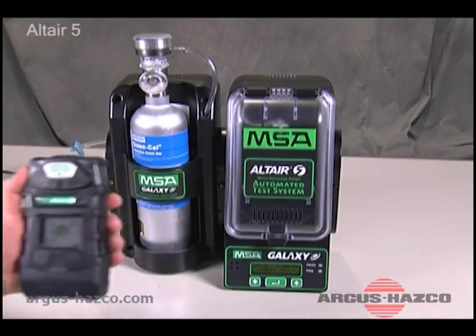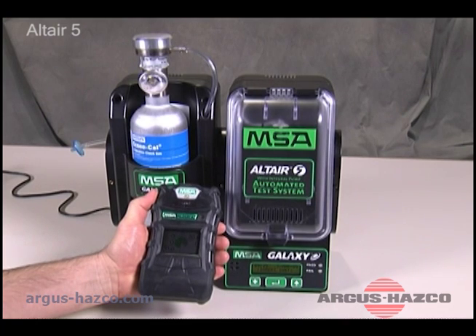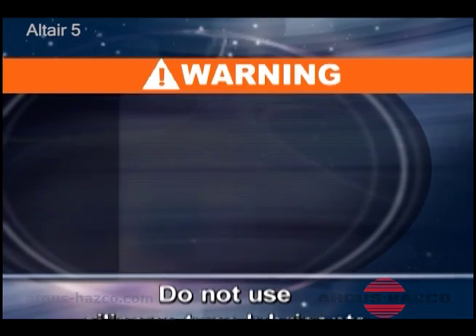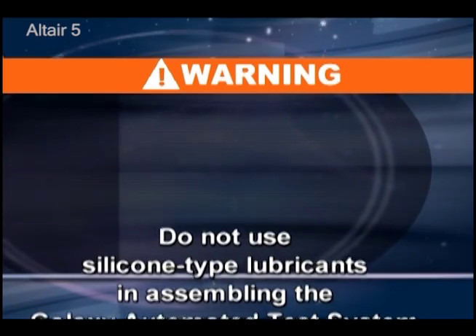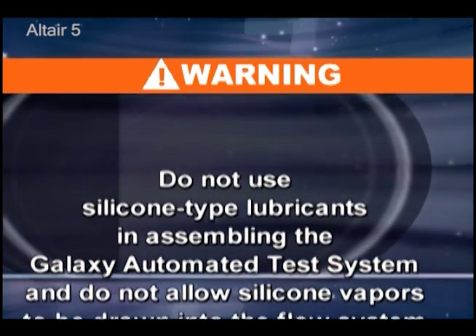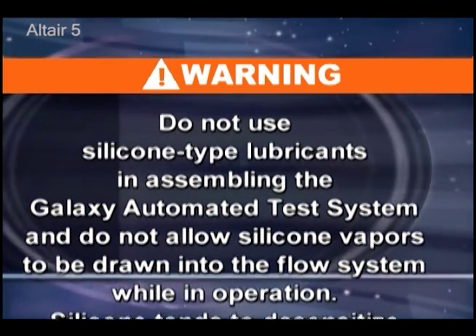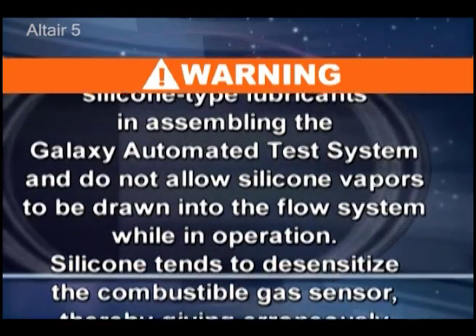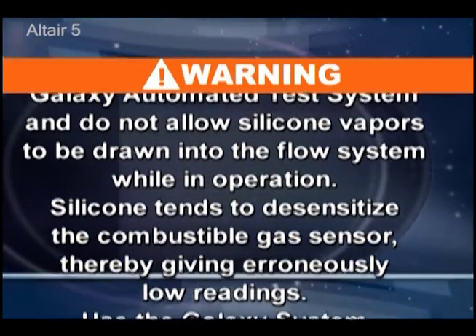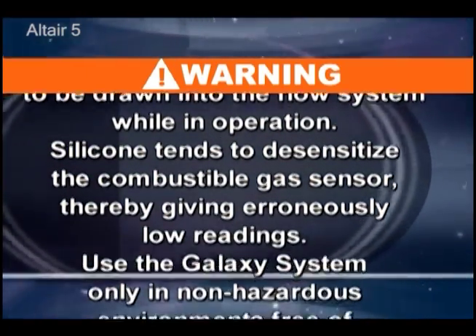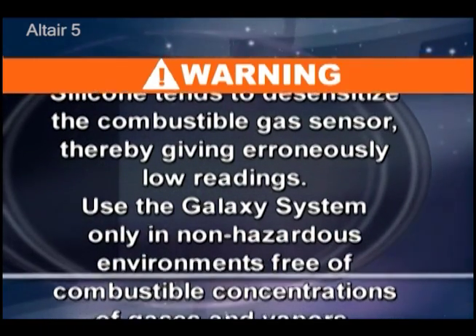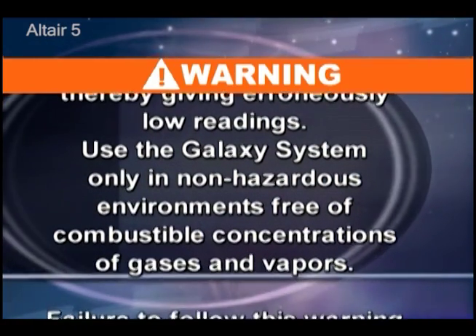Use the Galaxy test stand and calibration gas cylinder for automatic instrument calibration before each day's use. It's an easy procedure and should take less than a minute. Do not use silicone-type lubricants in assembling the Galaxy automated test system, and do not allow silicone vapors to be drawn into the flow system while in operation. Silicone tends to desensitize the combustible gas sensor, thereby giving erroneously low readings.